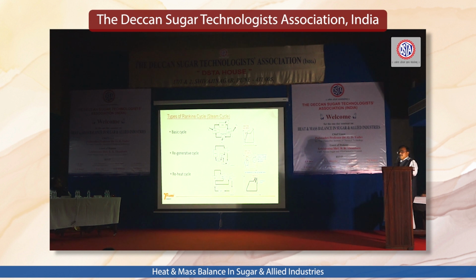With further progress and development, we came up with the regenerative cycle. In cogen, with the 2008 concept developed by the Maharashtra state government and Commissioner of Sugar, the 85 kg and 105 kg cycles evolved, and this regenerative cycle concept came up. In the regenerative cycle, we extract steam in the form of bleed at various stages for HP heater, LP heater and deaerator, and that steam is used to decrease the heat rate of the plant. This gives less fuel consumption and less bagasse consumption. This is used in high technology plants, such as 85, 105 and 125 ATA cycles.